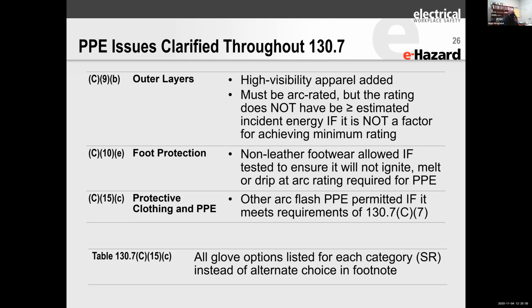If you have an 8-calorie exposure, you can wear a 3-calorie or 4-calorie vest over top of it. It needs to be arc rated, but it doesn't have to meet the hazard because the garment underneath it will meet the hazard as long as it's not a melting vest. So it says it has to be arc rated for high visibility garments. This helps for heat stress and things like that. Instead of buying an 8-cal vest and then putting it over an 8-cal shirt, you can buy a 3, 4, 5-cal vest for high vis, but it's arc rated so it won't melt or fly onto the face and melt onto the face.